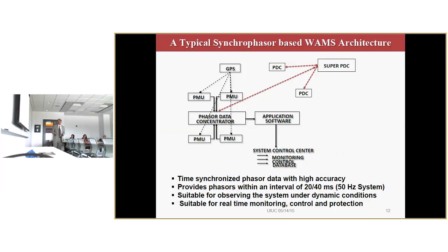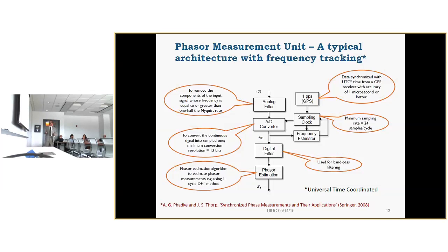That is the rate at which you can get the data from the field, and you can monitor the dynamic situation and also use it for various control and protection applications. Some detail about the phasor measurement unit, which is the field unit. After you get the analog data, you use an anti-aliasing filter, digitize it, apply a digital filter, and then use an algorithm similar to DFT or some other technique to estimate the phasor. But this phasor is defined with respect to the fundamental frequency. The fundamental frequency always changes, because the frequency is never a perfect 50 hertz or 60 hertz. So you have to estimate the actual frequency. So you need a frequency estimator and then a GPS clock for the time stamp. So that's about the phasor measurement unit.